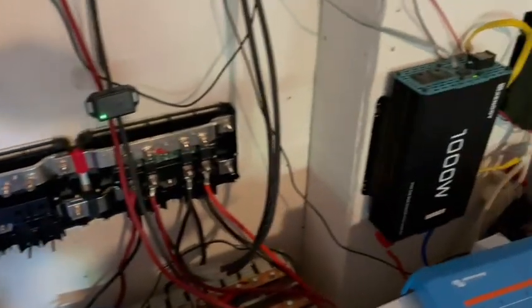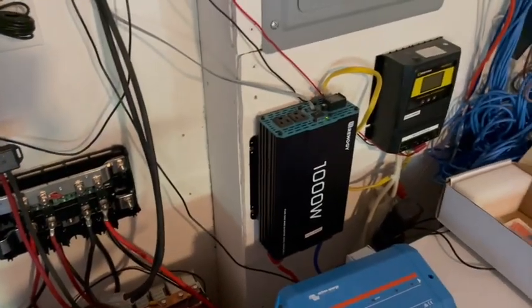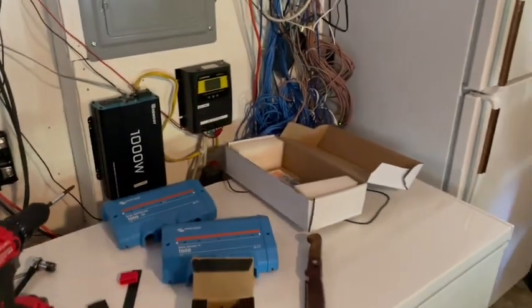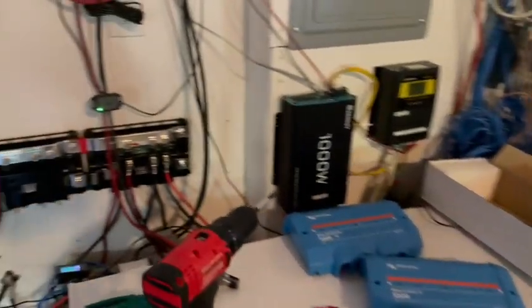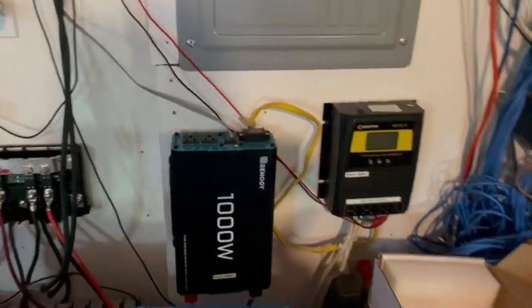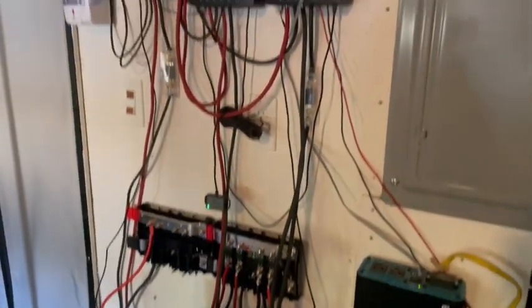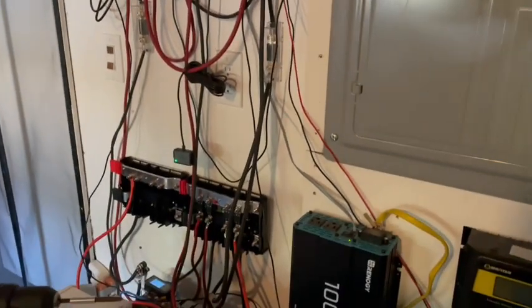And then these guys basically just run, get charged from those, and run that inverter, which runs these freezers and refrigerators here. When the refrigerators and freezers draw the batteries down below a certain set point, that automatic transfer switch will kick in and switch to wall power.